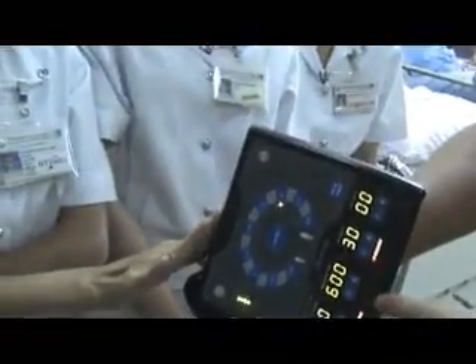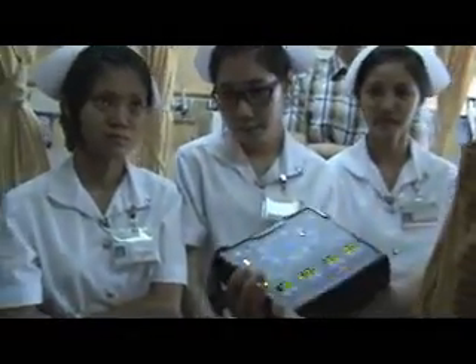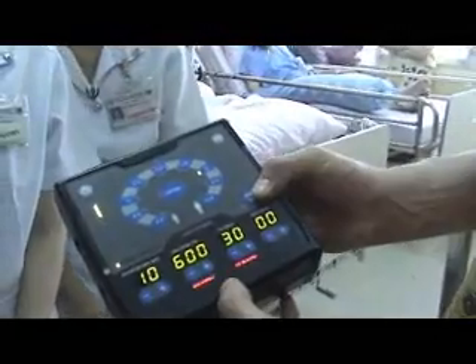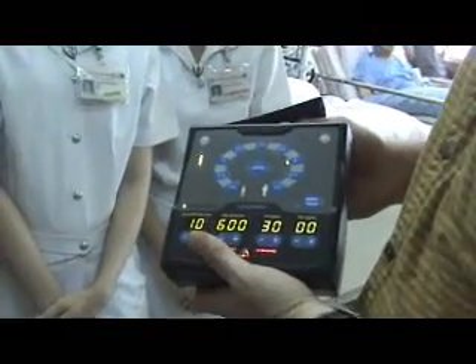As I took my finger off, it thinks it has much more space to ventilate, so it's giving a big ventilation cycle right now — you can feel that by placing your hand over it. Let's say you're doing CPR or resuscitating the patient. In those scenarios, you do not need ventilations while you're doing compressions. In that situation, you go to another function, confirm it, and activate a manual trigger, which allows the ventilator to give breaths in between your compressions — the normal ACLS protocol of two.